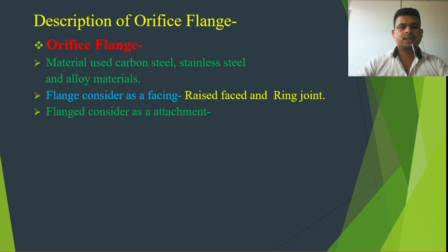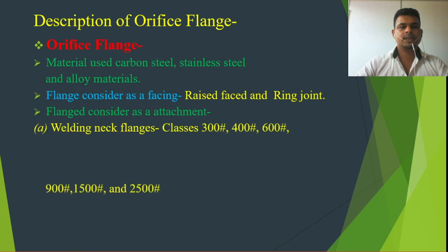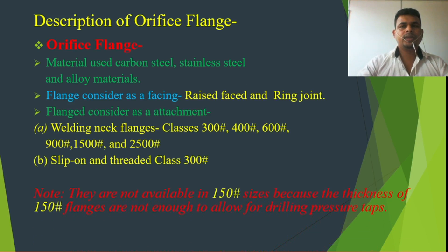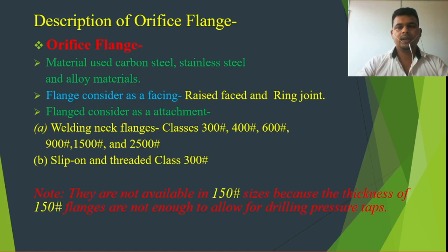If we consider flange attachment type, we can see weld neck flanges, slip-on flanges, and threaded flanges. So based on attachment, orifice flanges come as weld neck orifice flange, slip-on orifice flange, and threaded orifice flange. Slip-on and threaded orifice flanges are used for low pressure ratings. They are not available in Class 150 because the thickness of 150 flanges is not enough to allow for the drilling of pressure taps.